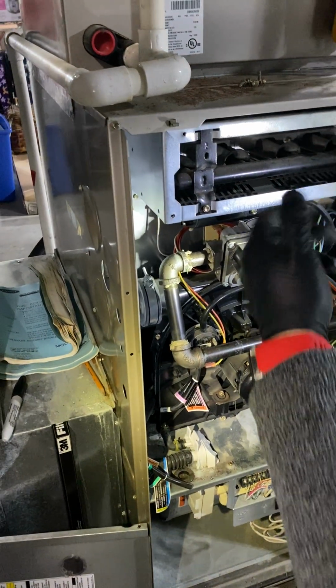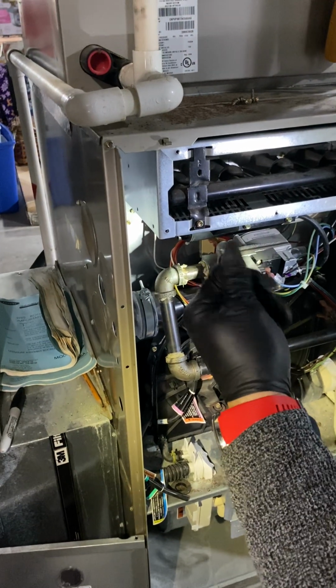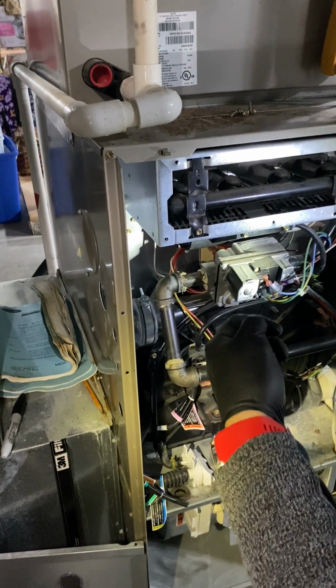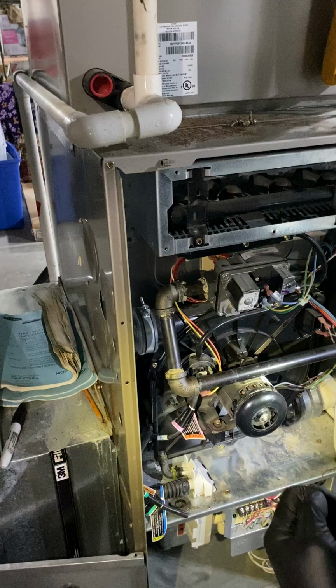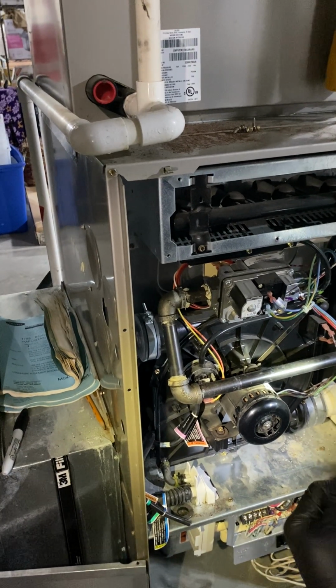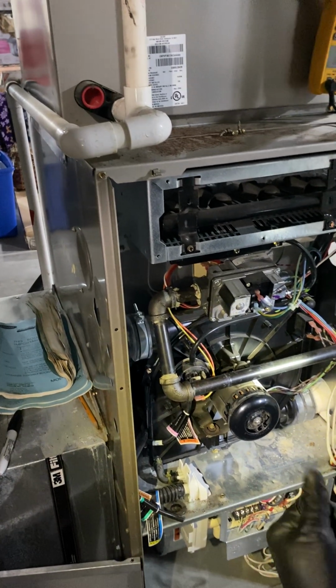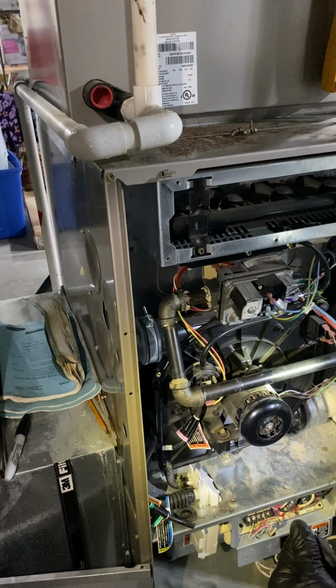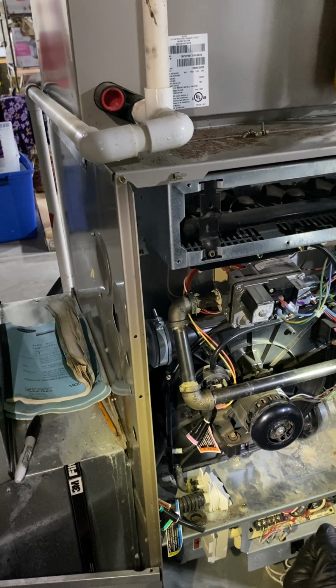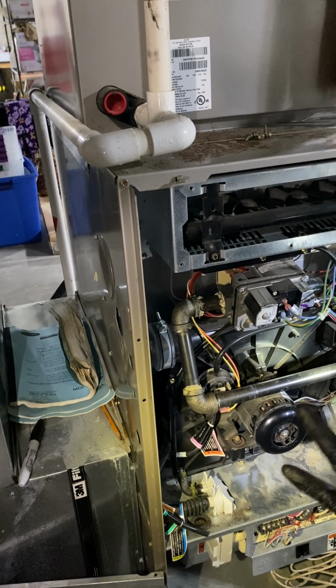The condensation, it's all flue gas, and it can be corrosive. If it sits in the back of the heat exchanger and doesn't all come out when it shuts off, it begins to eat away. Then it blocks the passageways from the primary to the secondary and clogs up the small holes.